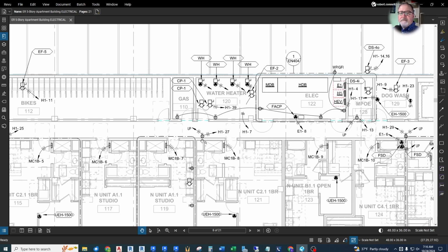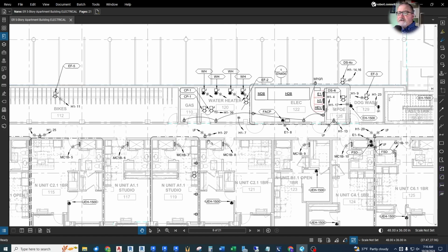If you figure there's only maybe 10 feet between floors, that's fairly economical versus trying to run my circuit all the way down this hallway. So, I mean, we have to go from here clear back to H1 first, but then from there on, we just go up to the rest of the receptacles. So that's one kind of circuiting technique we use.